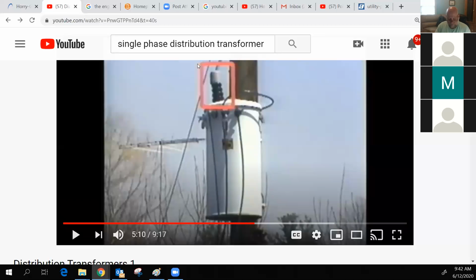the conductor comes in on this side, goes through the windings on the core, comes out the top on this side, and goes to a pole ground. The problem, I say it's a problem, I have seen it before, but I've seen guys go out, change out transformers, and forget on a single bushing transformer to connect this ground back to the neutral or the pole ground. And if you do not have this connected back, then you could have, we use 13,200 volts. You might have 13,200 on this tank right here. So you had to be very careful with your checks before you energize these transformers to make sure that this was connected to the pole ground.